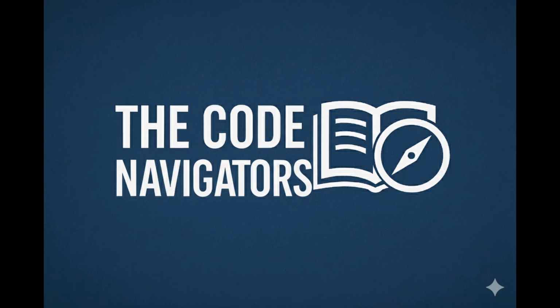And then 1020.5 deals with dead ends, a corridor where you can only go one way. The dreaded dead end. The limit is 20 feet. 20 feet. That's how far the code thinks you can walk before you realize you're trapped and can still safely turn back. But with sprinklers, it's extended to 50 feet. Again, the sprinklers control the fire at the entrance to the corridor, giving you time to get out of that 50-foot trap.